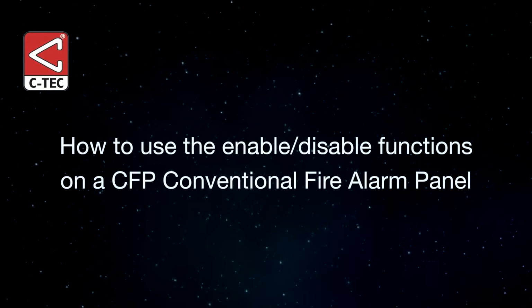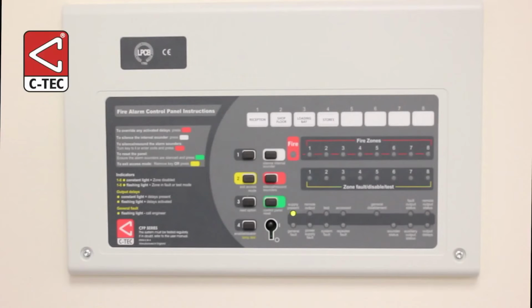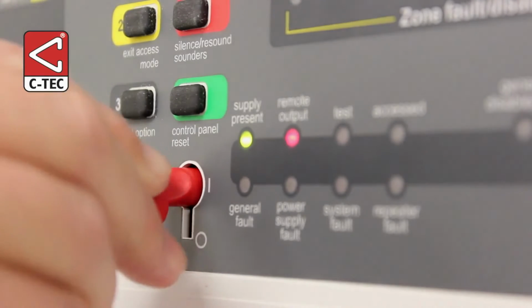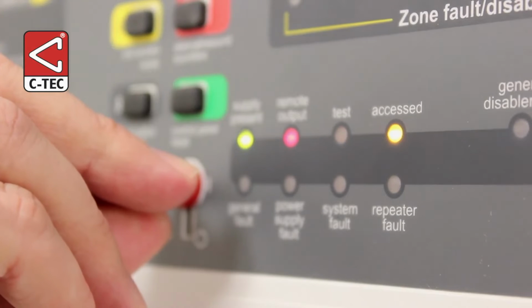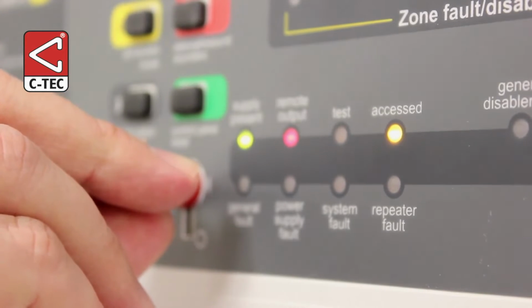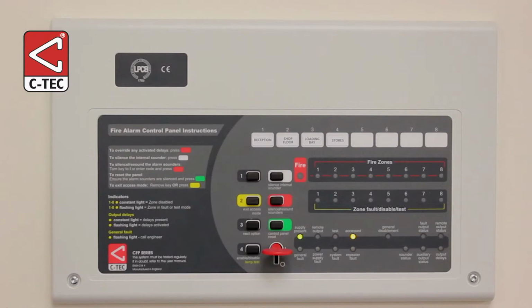How to use the authorised user controls on one of C-TEC's CFP fire panels to enable and disable zones or other functions. To gain access to these controls, you must first put the panel into access level 2. You can do this using one of two methods: entering a secure code using the panel's keypad or turning the key switch. The access light will turn on to indicate the authorised user controls are operative. You can enable and disable the functions you require using a simple selection process.